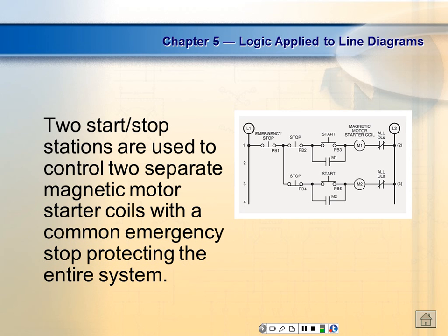I know it's a motor starter, not because of the M, but because of that guy right there. It's because it's got the overload in series. So it might be called number 2 motor. It might not be, it could be called all kinds of things depending on the company that puts the thing together. Are we okay here? So if you see an overload on the right side of the relay, then that relay is a motor starter. If you don't see the overloads, then it depends on what it does. If all the contacts for a relay stay inside the control logic, it will be called a control relay. If it controls power outside of it, it would be called a contactor. So that's the nomenclature. Of course, when you go to work, you use the terms they use, right?